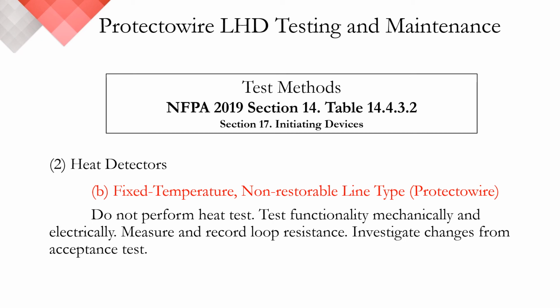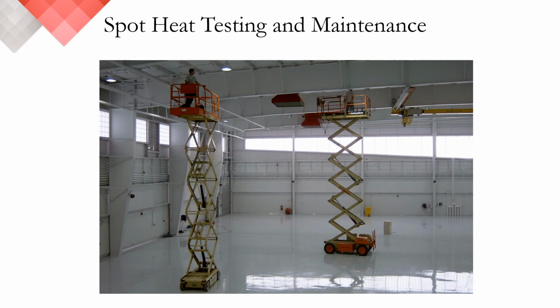Just be sure that all solenoids and auxiliary functions are disconnected during the testing of Protectowire. We do not want any unwanted discharges, releases, shutdowns, or signaling. Having just discussed the NFPA 72 annual requirements for testing Protectowire, I want to now turn to the practical advantages of using Protectowire. With Protectowire, you can locate the end-of-line box and short out the detector.